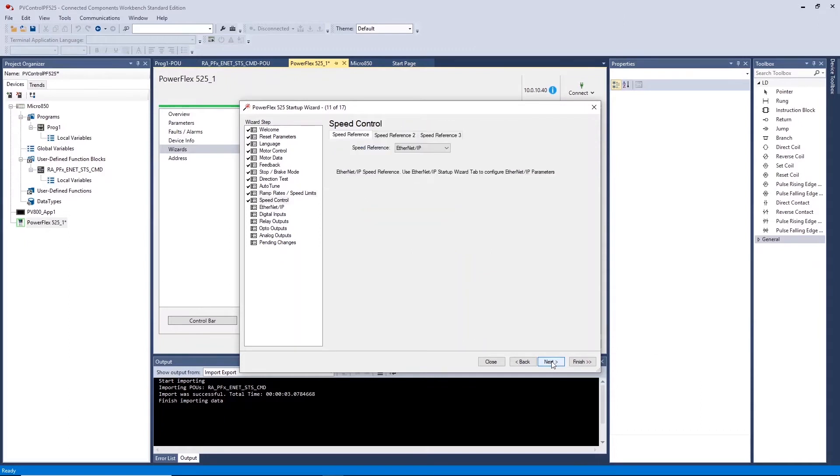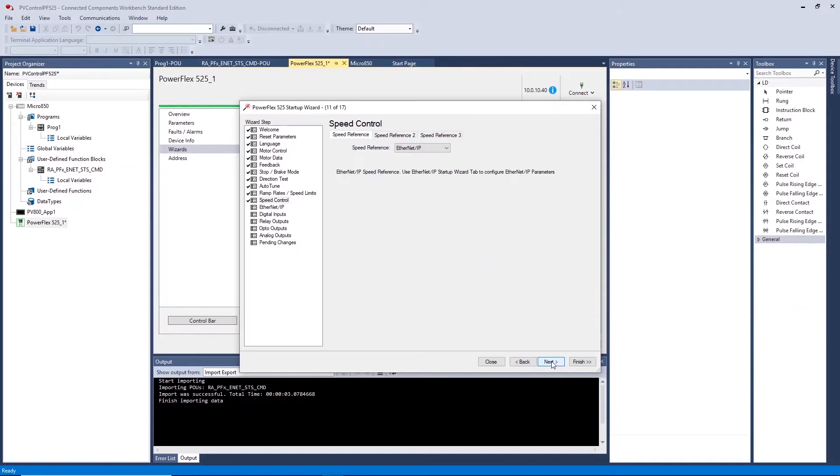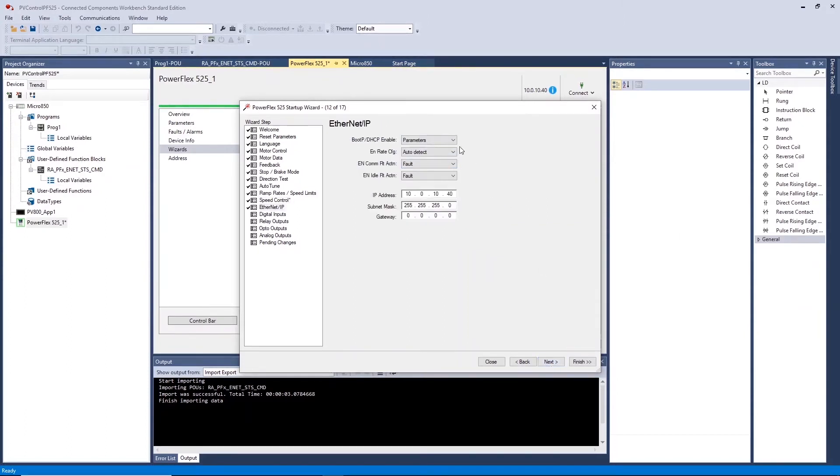Ensure speed reference 1 is set to Ethernet IP in order to control the speed setting from your HMI. Ensure the Ethernet IP settings are correct to allow continued communication with your drive.